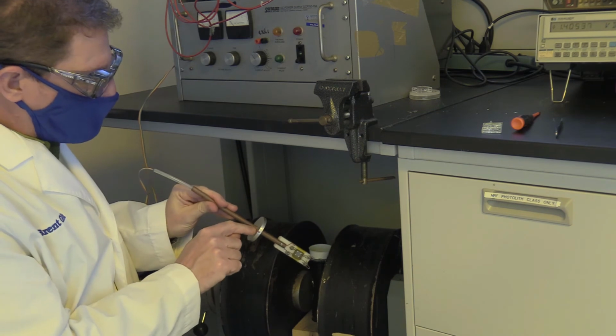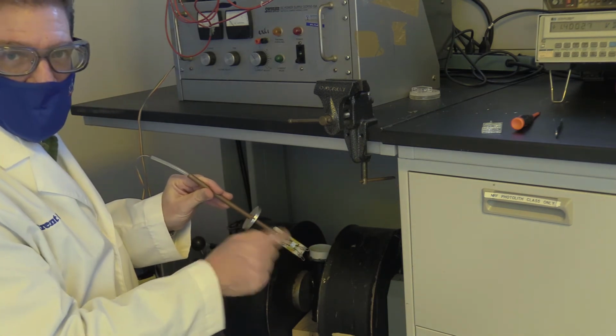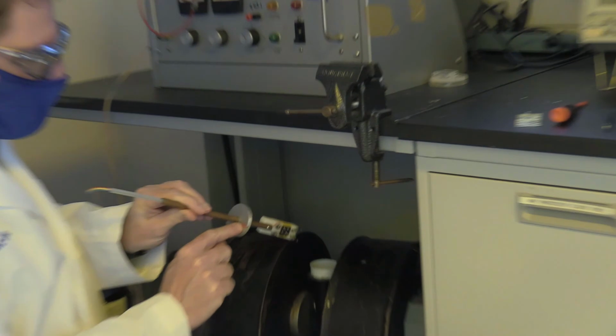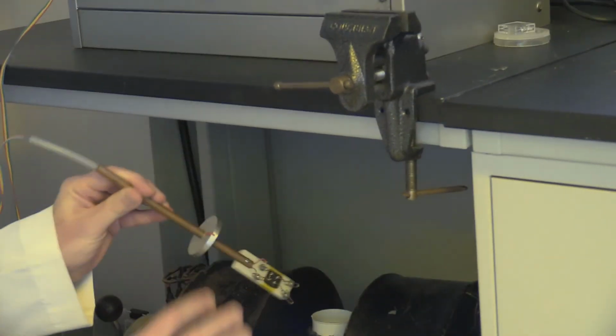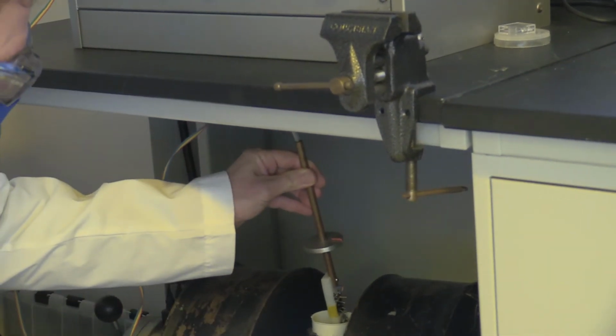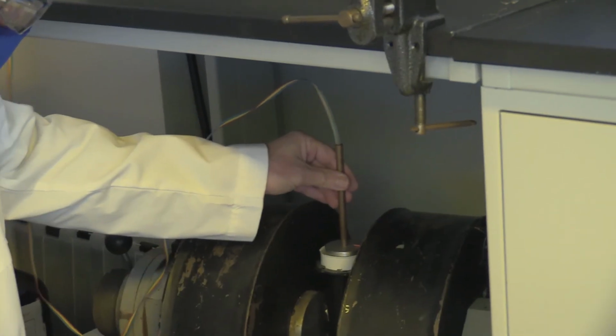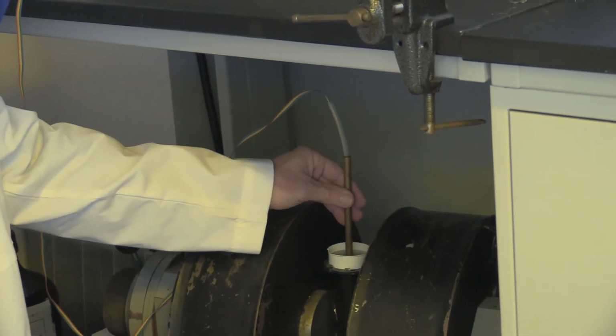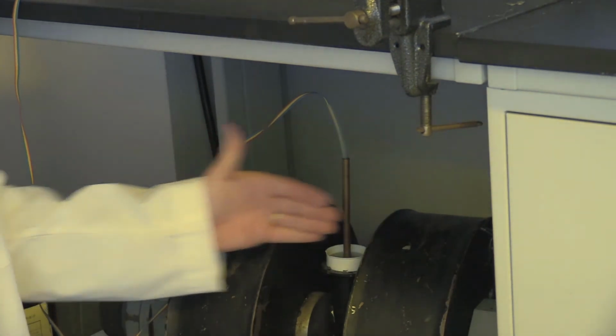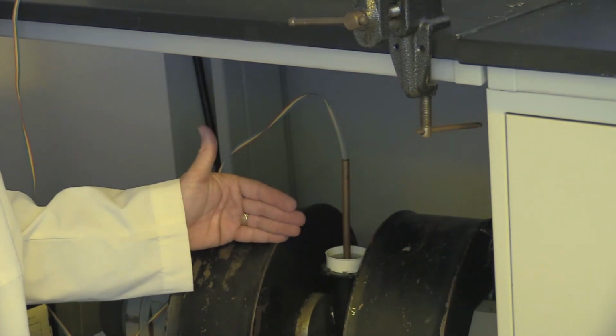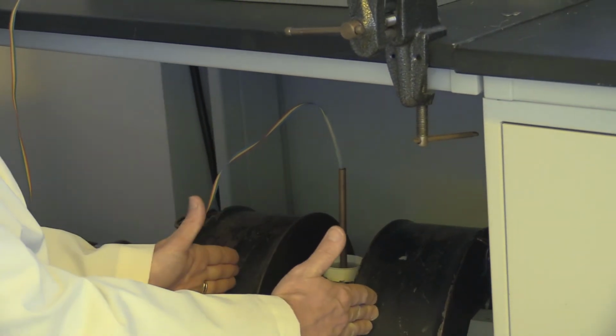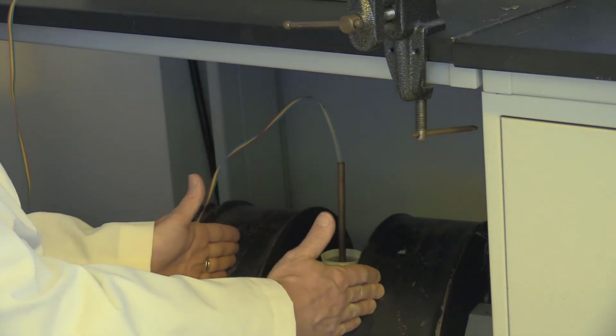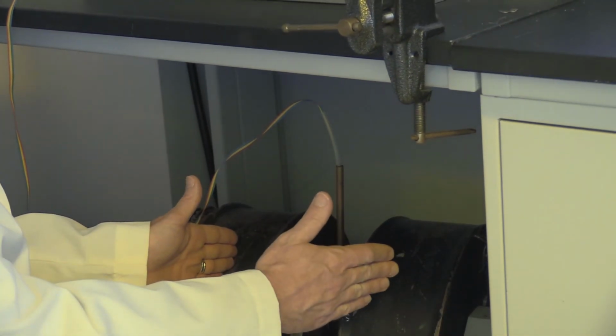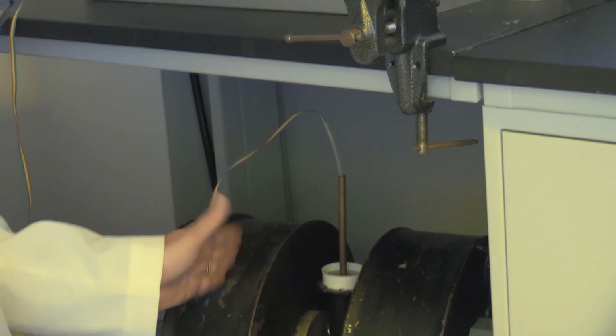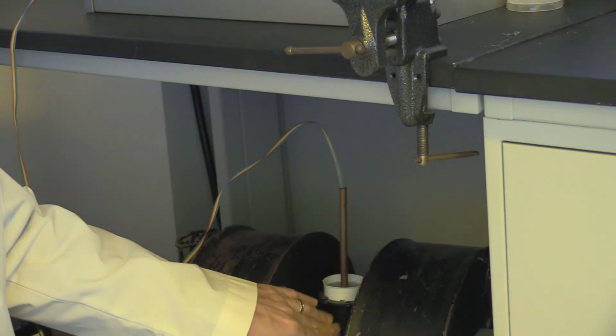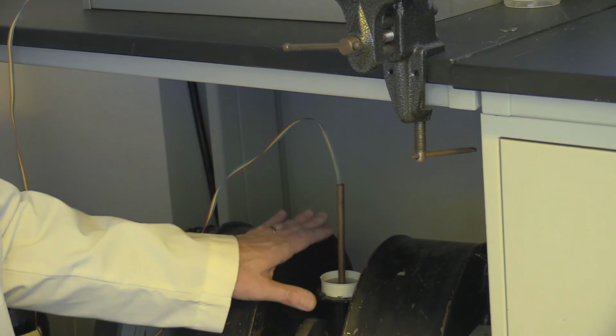This red wire here indicates the face of the sample, right? This little fine little red wire here. And this whole probe then gets inserted between these 2 poles in this case. You want to ensure that the red wire is in the same direction as the 2 poles. This way you have a north and a south field, or a south and north field, depending on the direction of flow of the current in the magnet. This container is covered in tape, so it's nice and opaque, which keeps the light off the sample.